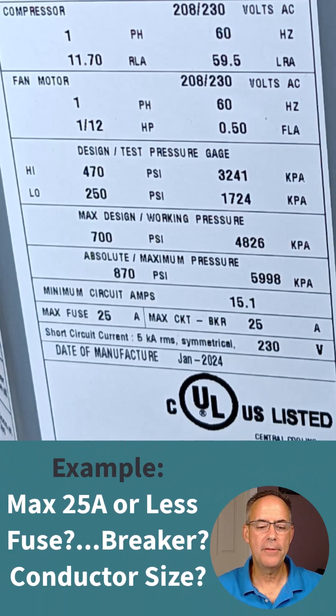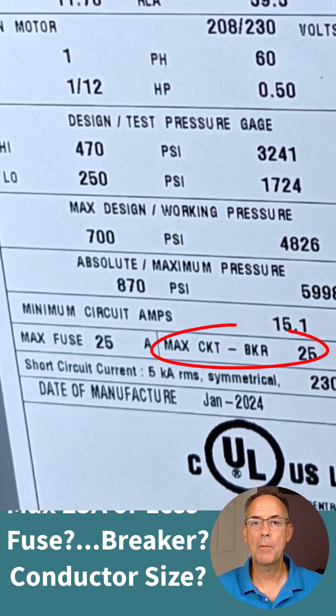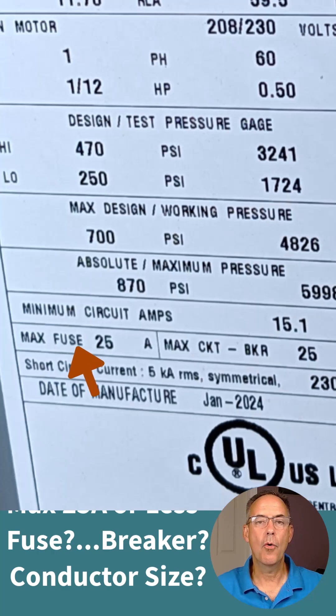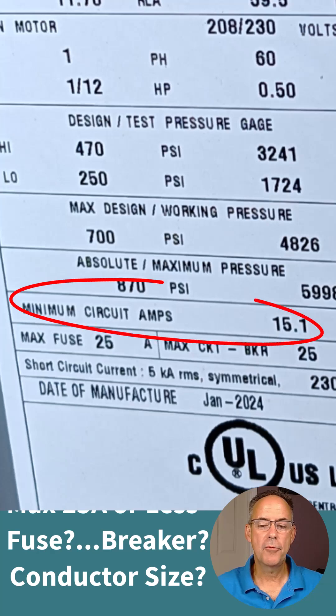Let's walk through a couple of examples. On this tag it tells us maximum fuse 25, maximum circuit breaker 25. The tag can say fuse or circuit breaker, or it can say both, meaning you can use either. On this particular tag we'd be able to use either a fuse or a circuit breaker.